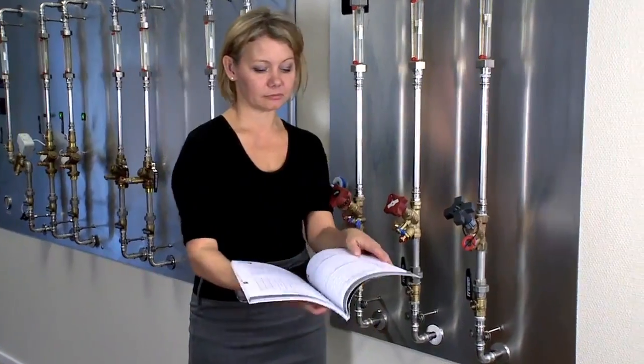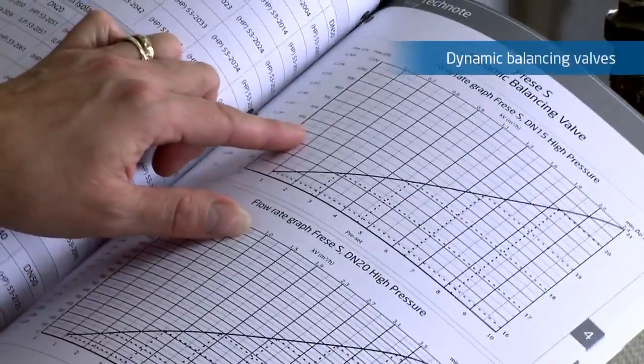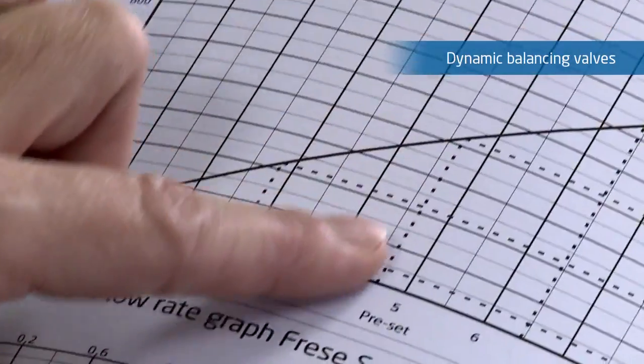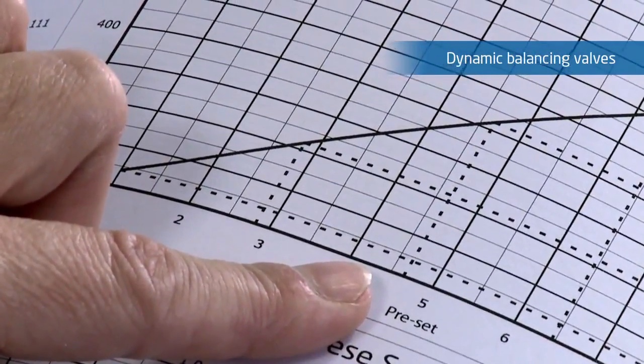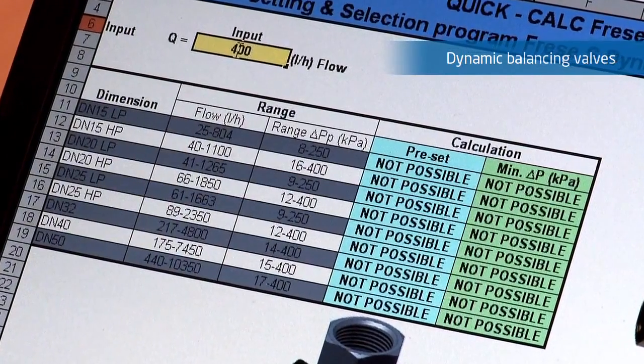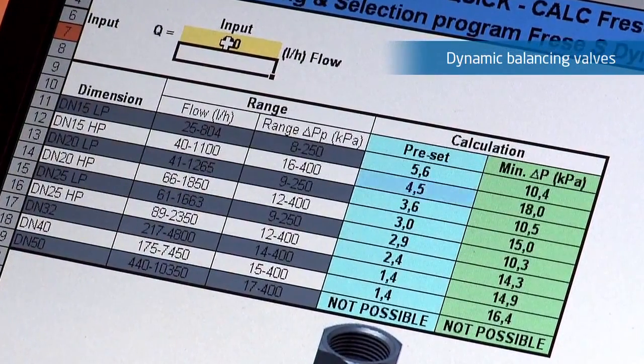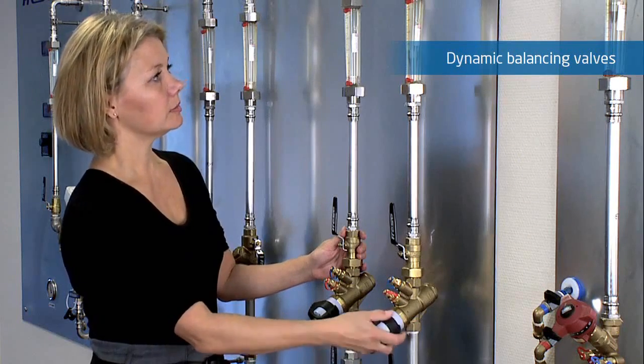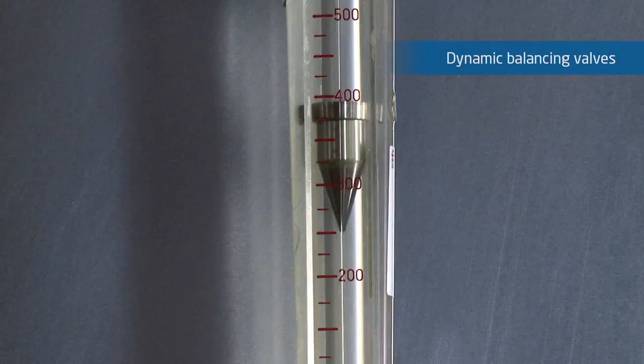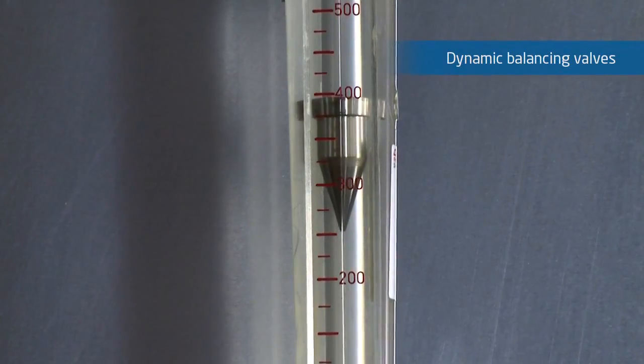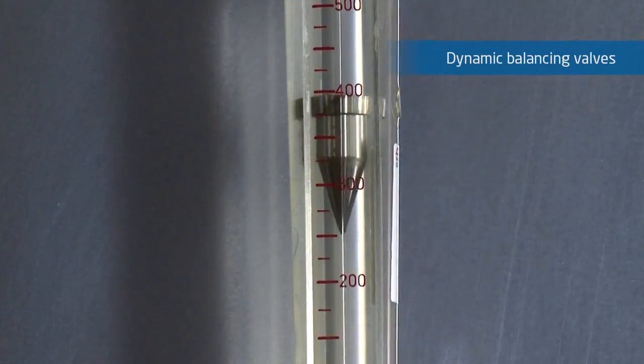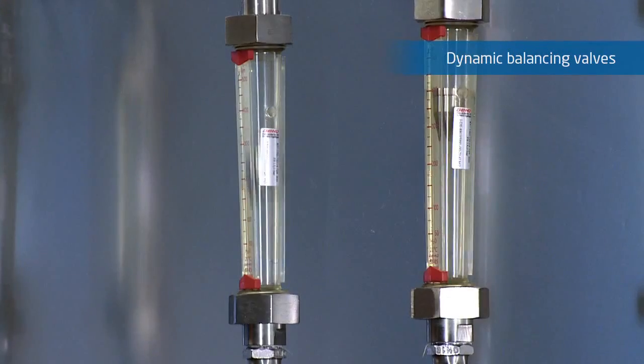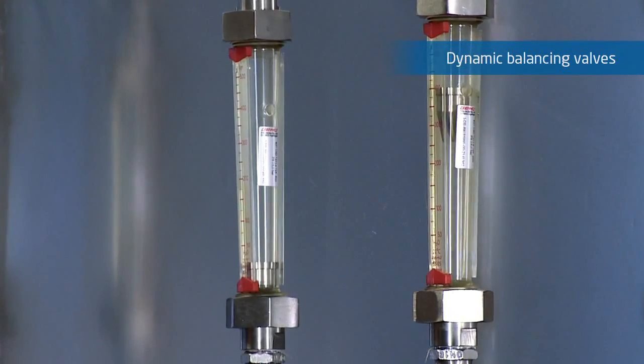The entire process is completely different in systems fitted with dynamic balancing valves. You can simply set the flow using a graph — no measurements. Alternatively, you can enter the desired flow into a software program that calculates the set point for the valve. The valve can then be set to the correct set point and the desired flow is achieved. In contrast to the static balancing valve process, when a temperature control valve changes position, the flow in other parts of the system is not affected.